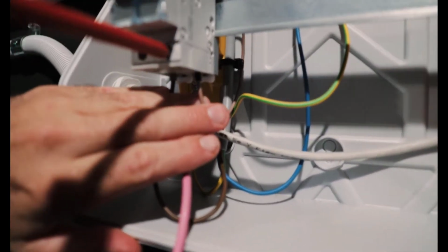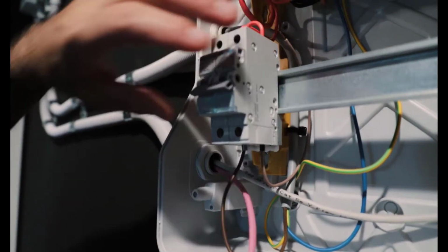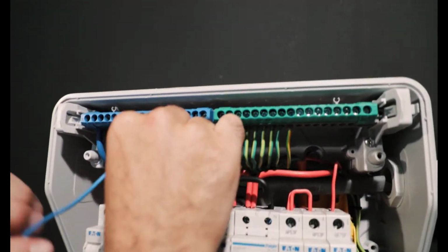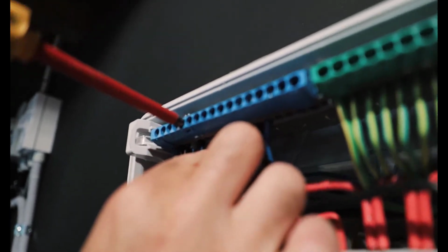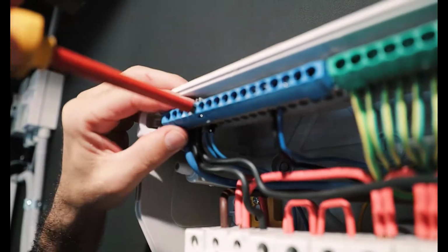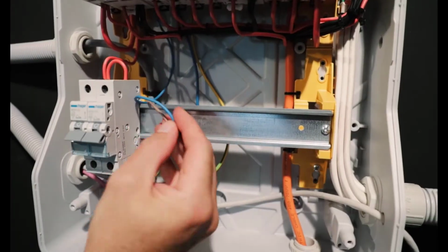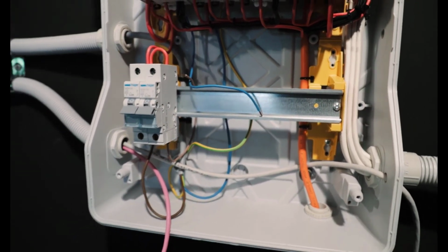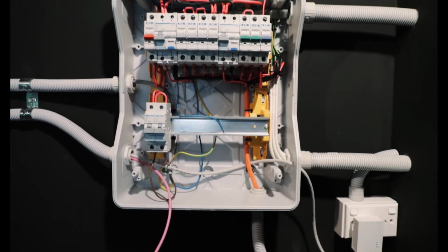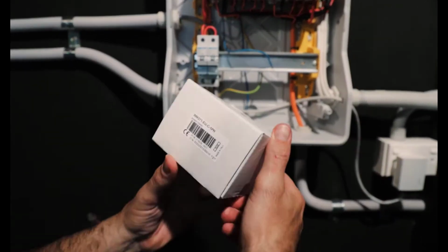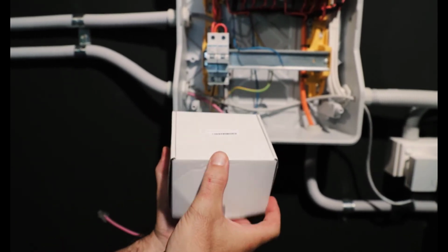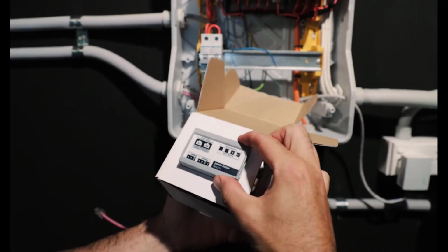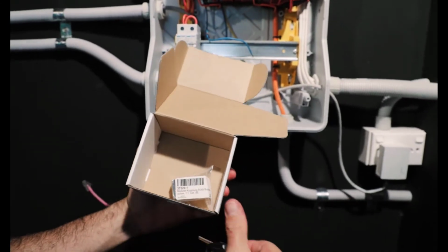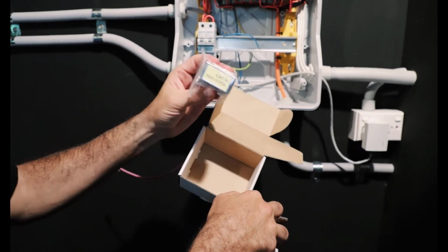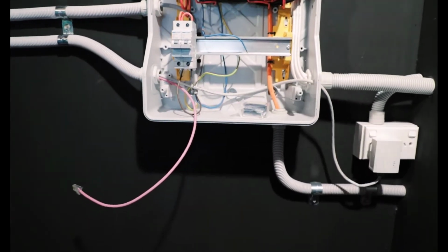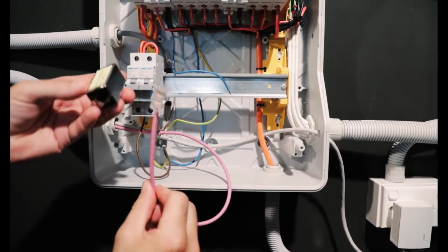So now we're just wiring up very quickly the wiring for the actual meter itself. So active, neutral. And then here we're going to bring the meter in. So these come as part of the accessory kit. And it already comes with a section of the Modbus cable pre-wired into it, and a connector to be able to reconnect the Modbus to the supply, which we run back to the sonnen system.